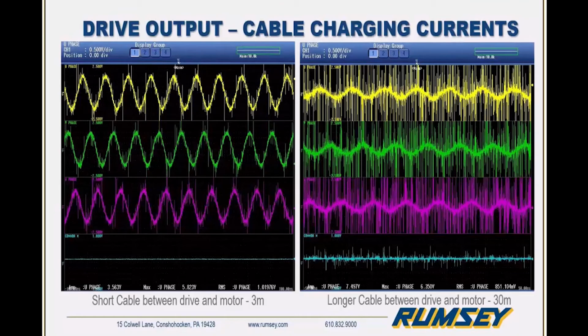So I can jump in there a little bit, Jared. Just from a reference standpoint, if you're just using standard cables, non-shielded, you're not allowed to have more than 3 sets of motor leads in one conduit, or you will get crosstalk and you'll get voltage kind of passing between the cables, and you'll definitely notice that. So there are guidelines within the installation of no more than 3.